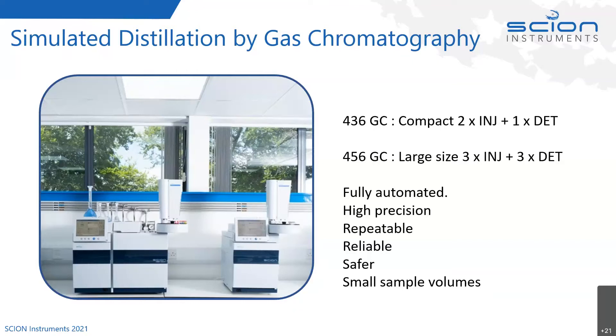Both ovens can accommodate 7-inch GC columns and use traditional nut and ferrule connectors. So you can use columns not just from Scion, which they do sell, but from other manufacturers as well. If you've got old traditional columns, they'll fit in both the 436 and the 456 GC.